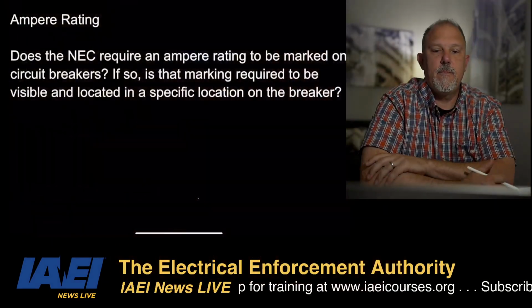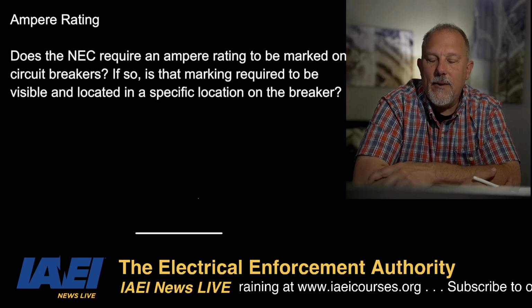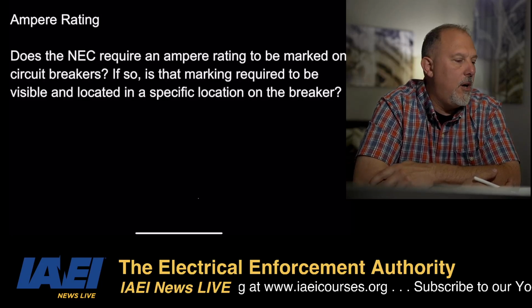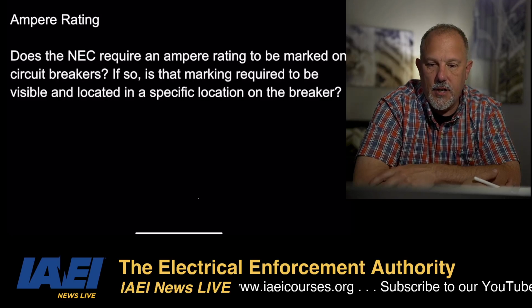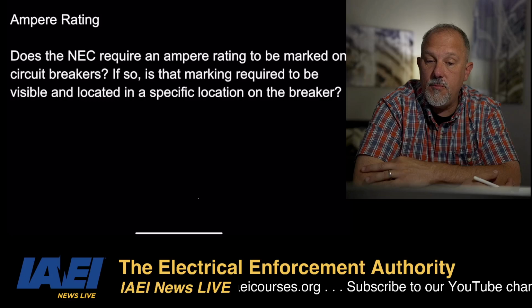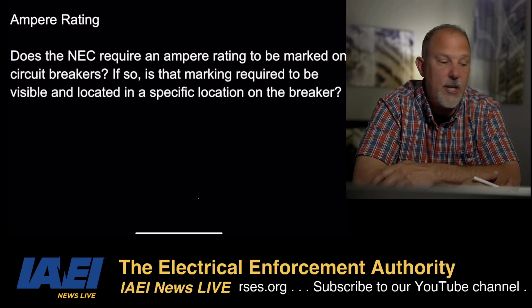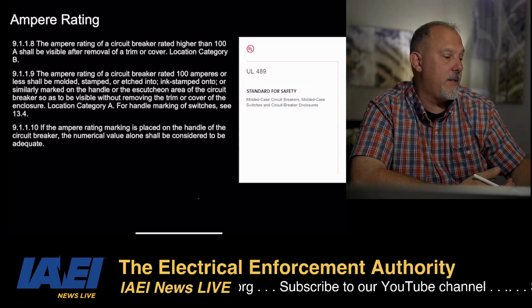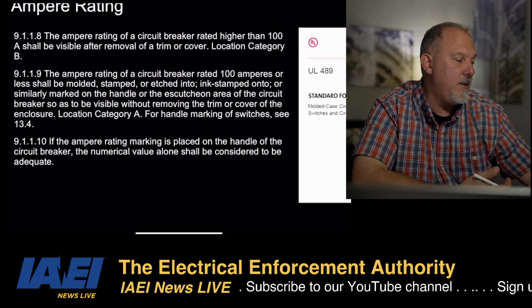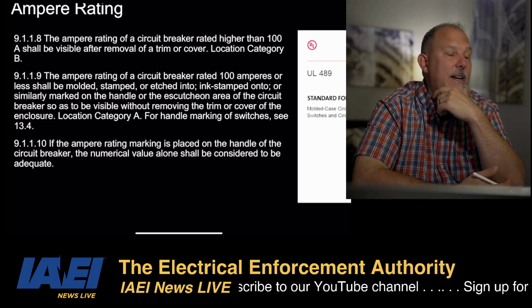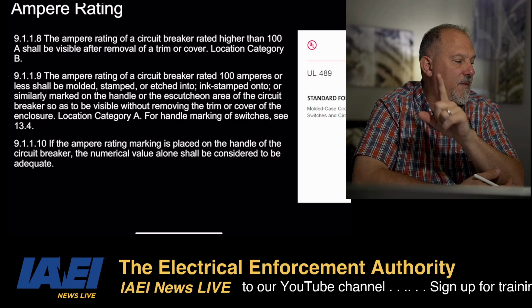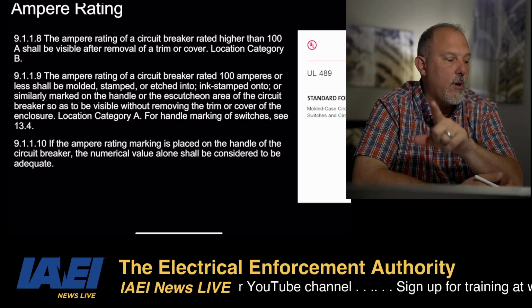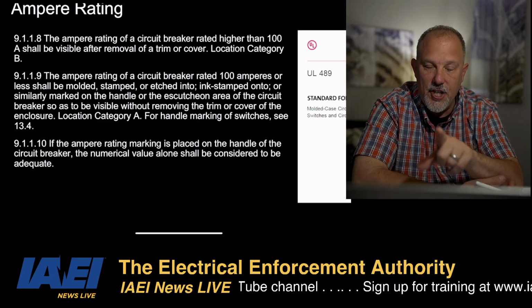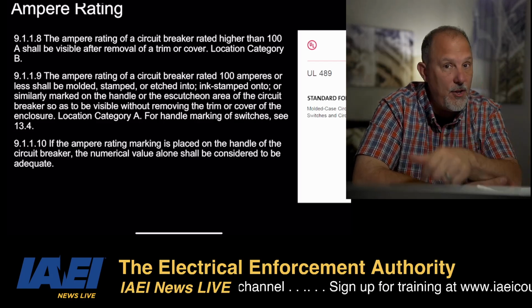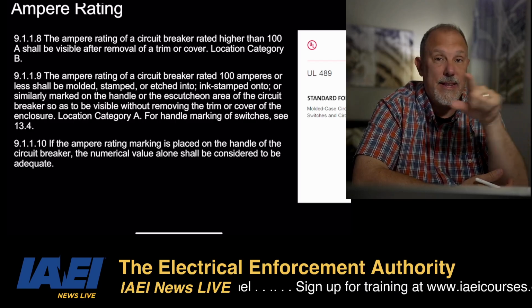Does the NEC require an Ampere rating to be marked on circuit breakers? If so, is that marking required to be visible and located in a specific location on the breaker? We already went through this. So here's the Ampere rating. The Ampere rating of a circuit breaker rated higher than 100 amps shall be visible after removal of a trim or cover. Okay, location category B. Remember, we went through that. You can rewind this video and take a look at that table.